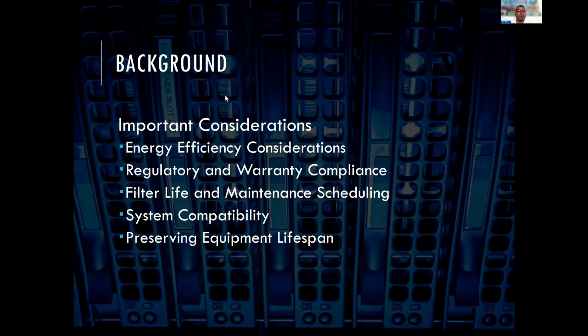Relationship with the manufacturers, understanding what the equipment calls for and what the manufacturer is recommending. Also getting feedback from engineers and architects, and also getting feedback from a quality filter supplier, somebody who understands the industry and understands how to properly size and suggest equipment. Other things that we're going to look at: filter life, maintenance scheduling, making sure you're changing that product for the best possible energy efficiency solution, not necessarily when we're hitting that 1.0 or 1.2 or 1.5 on a Magnehelic.